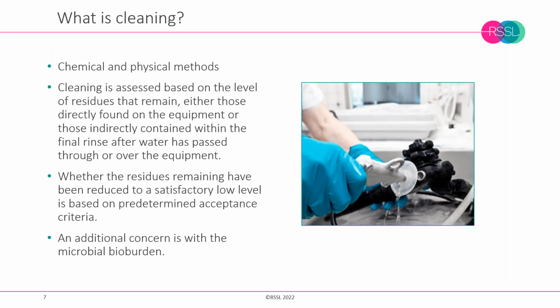Okay, so to begin with, what do we mean by cleaning? Well, cleaning is a combination of both physical and chemical means to achieve a required level of cleanliness. So the physical methods include mechanical or manual operations supported by physical techniques such as emulsification and dissolution. Chemical methods include the use of solvents and chemical agents to achieve the solubilization of materials and through the act of rinsing. And cleaning is assessed based on a level of remaining residue that's set below the predefined acceptance level.